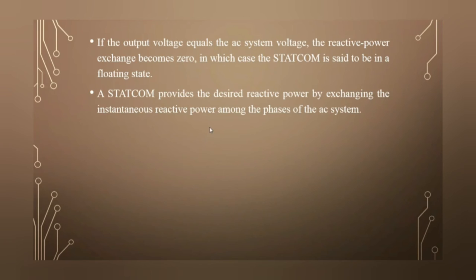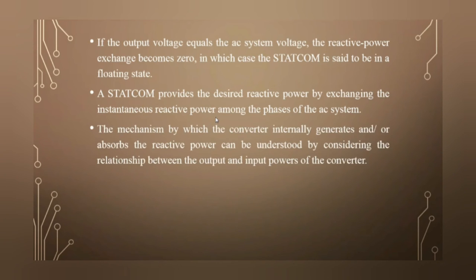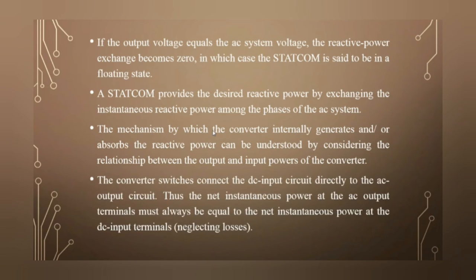A StatCom provides the desired reactive power by exchanging the instantaneous reactive power among the phases of the AC system. The mechanism by which the converter internally generates or absorbs reactive power can be understood by considering the relationship between the output and input powers of the converter. The converter switches connect the DC input circuit directly to the AC output circuit; thus, the net instantaneous power at the AC output terminal must always equal the net instantaneous power at the DC input terminal.